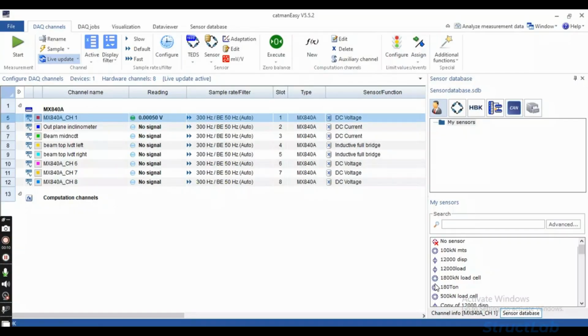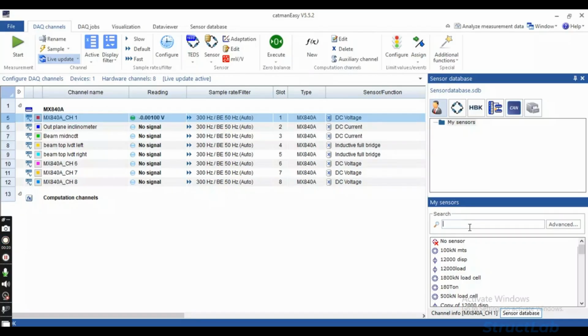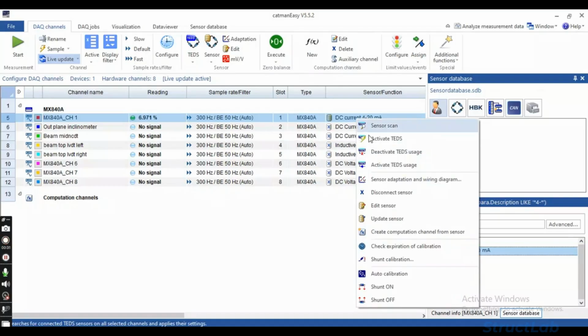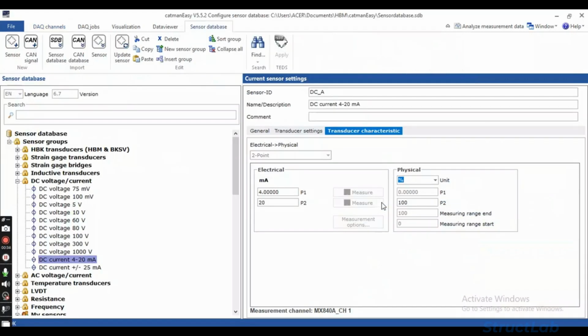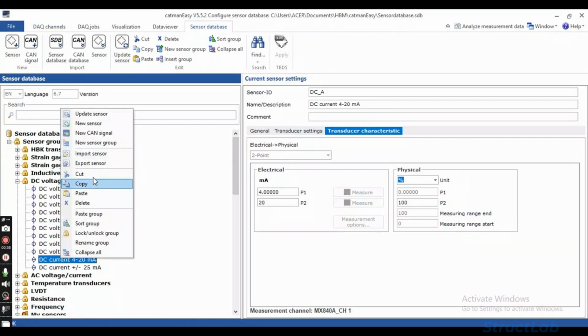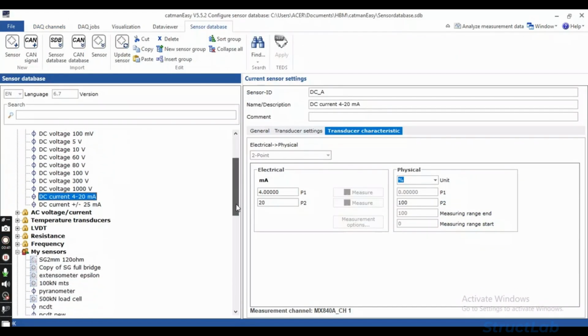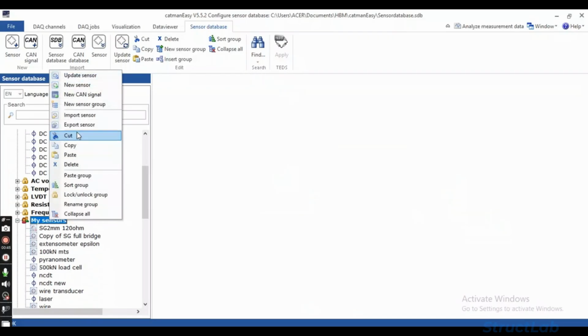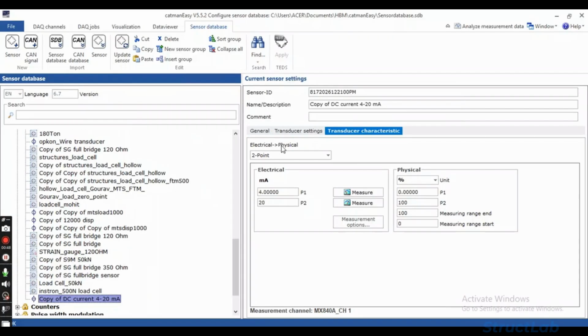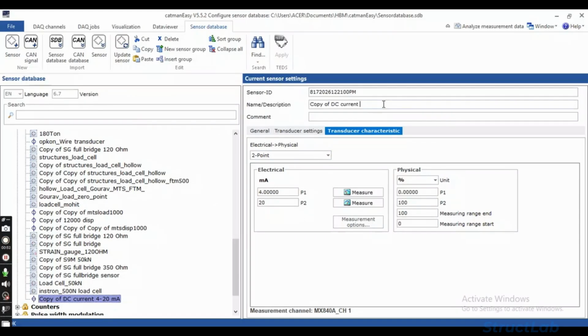Once the software is launched and the project loads, locate the channel in the channel list where your sensor has been connected. To configure the sensor, search the sensor database on the right for your predefined template, or right-click the existing current sensor template and select Edit Sensor to verify or modify its parameters. Now in the sensor database window, right-click and copy the existing current output sensor template and paste it in My Sensors folder. Rename the new entry, let's say NCDT_current analog output.